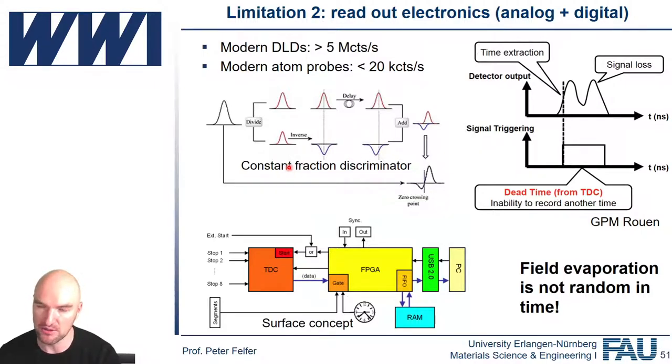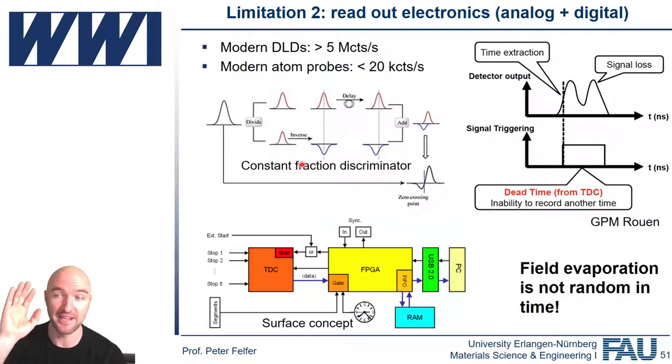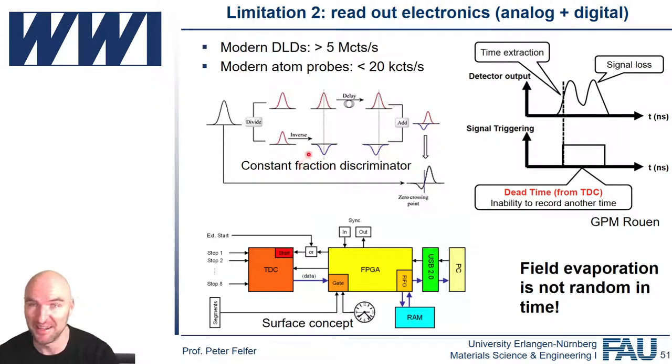The problem with the constant fraction discriminator is, what happens if we have two pulses that are very close to each other? Can it distinguish them? The dead time of such a constant fraction discriminator is roughly about 3 nanoseconds on a modern one. And this is a severe limitation for multi-hit capacity. In our older detectors, it was even worse. 3 nanoseconds is already pretty good.